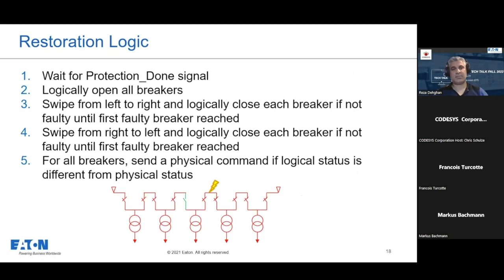So here's the general logic for the restoration. We wait for the protection done signal. We logically open all breakers. And by logically, it means we don't send any commands. Internally, we have some bits for each of the breakers, and we put them at 0. Then we start swiping from left to right, and logically close each breaker, if not faulty, until the first faulty breaker is reached. So we swipe from the left side, we stop, and then we start from the right side. Again, we swipe from right to left, and logically close all the breakers until we see a faulty breaker.